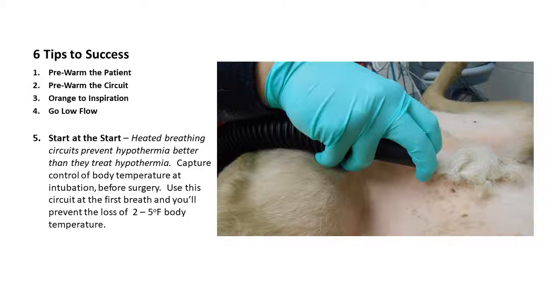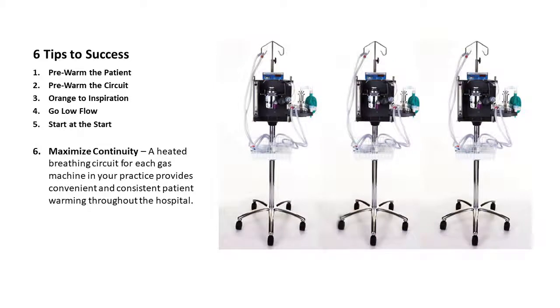Tip number 5, start at the start. Heated breathing circuits prevent hypothermia a lot better than they treat hypothermia. To better capture control of the patient's temperature, use the heated breathing circuit from the very beginning, at induction of anesthesia, at intubation. Use this circuit at the first breath, and you'll prevent the loss of 2 to 5 degrees Fahrenheit body temperature. And tip number 6, maximize continuity. A heated breathing circuit for each gas machine in your practice provides convenient, consistent, and effective patient warming throughout the hospital.